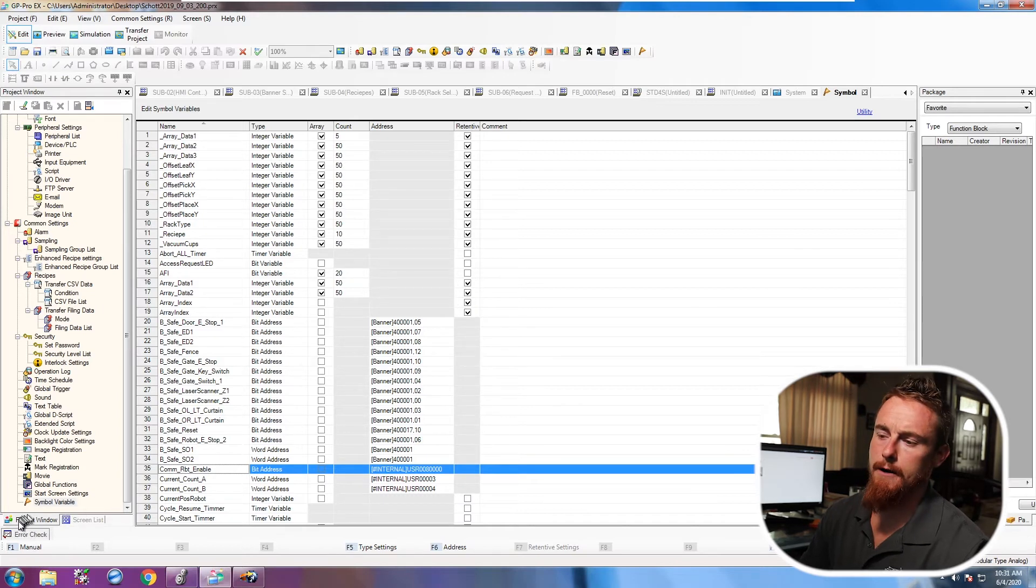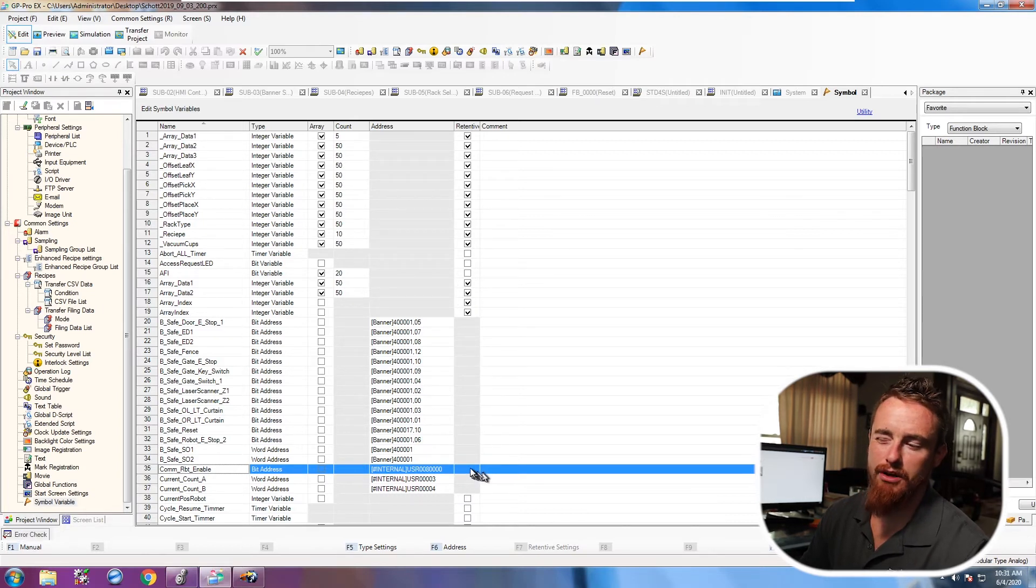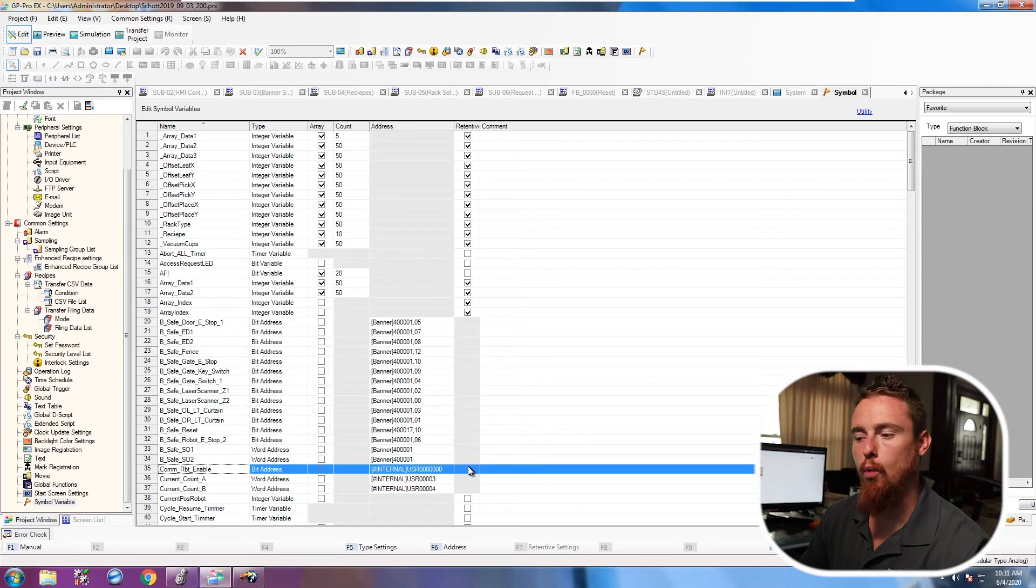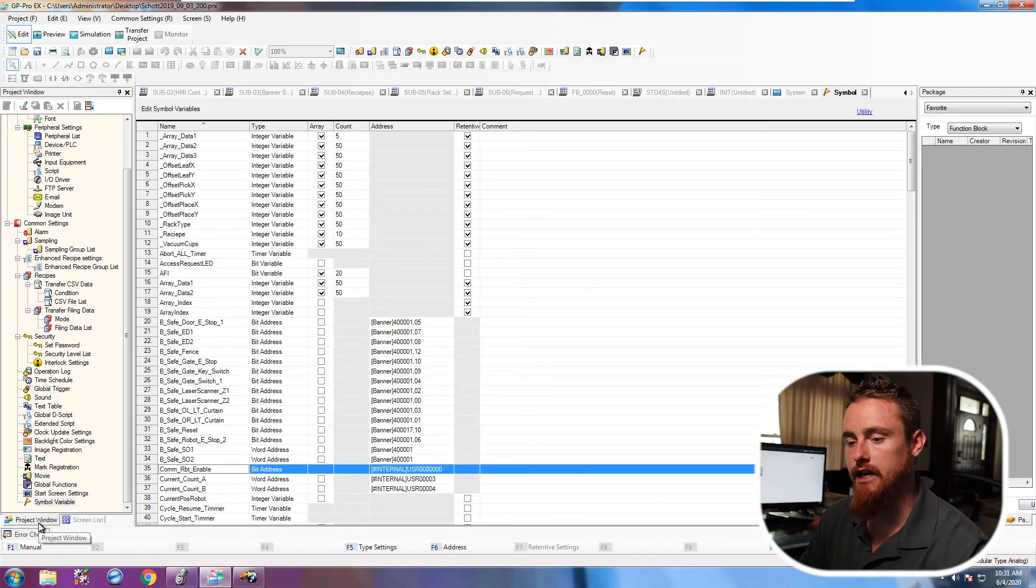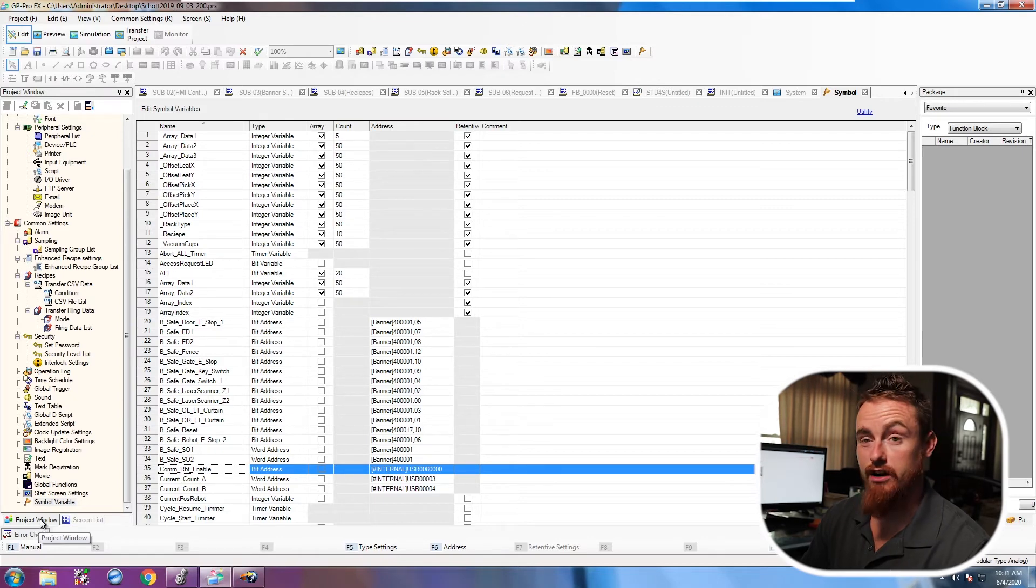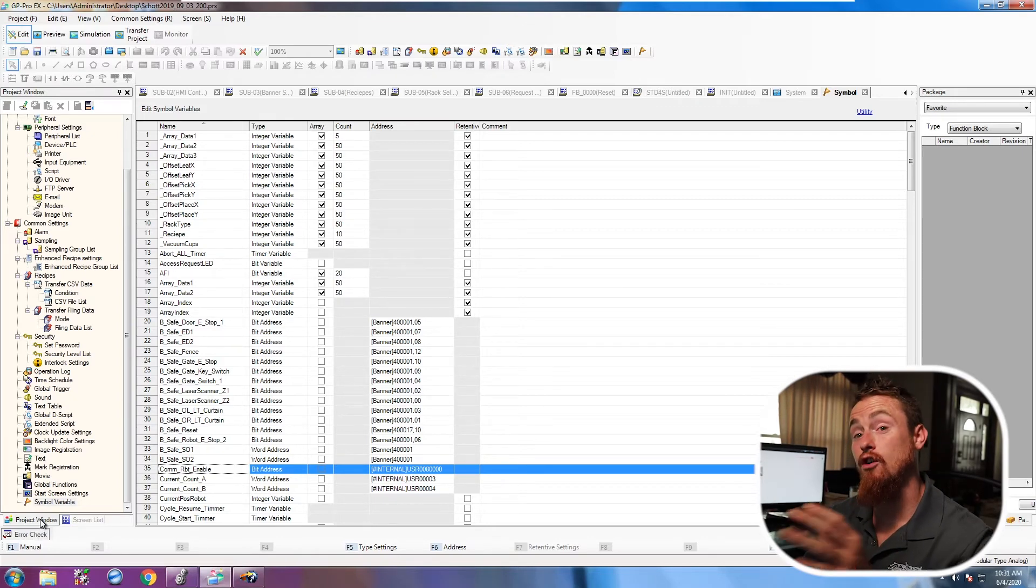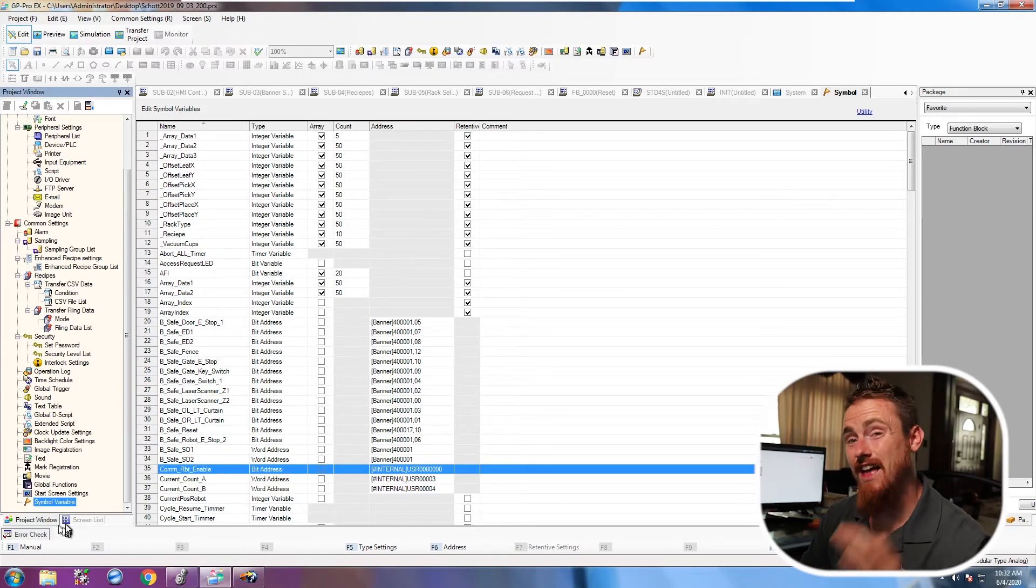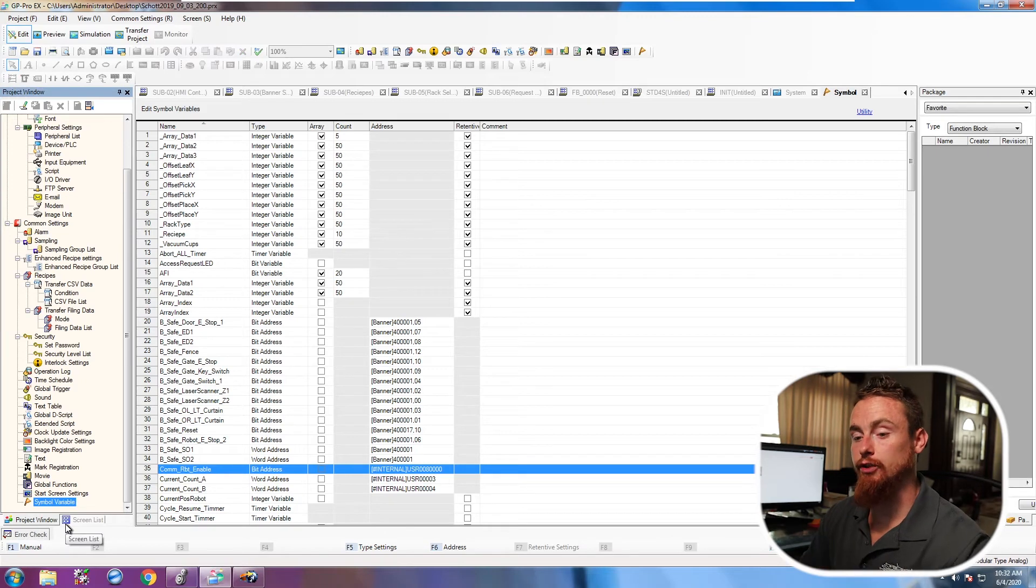And then you maybe not have to put it in the logic. You just put a 1 in it, make it retentive, and then nothing should ever manipulate it to make it not go true. But it's kind of a scary route to go too because if something does ever make it go false, then that could really be an issue.